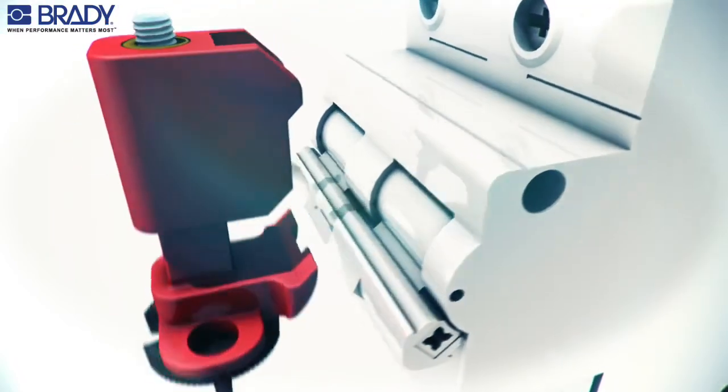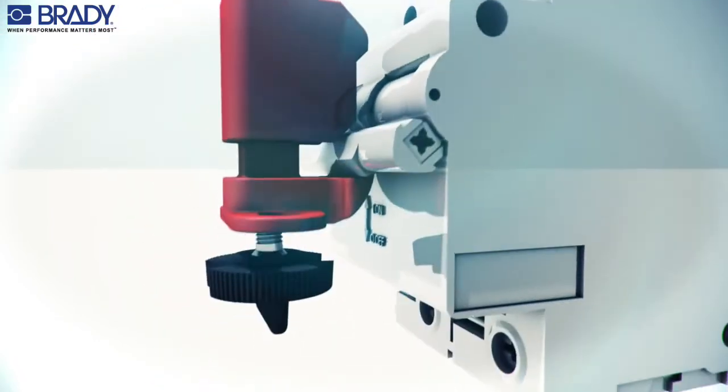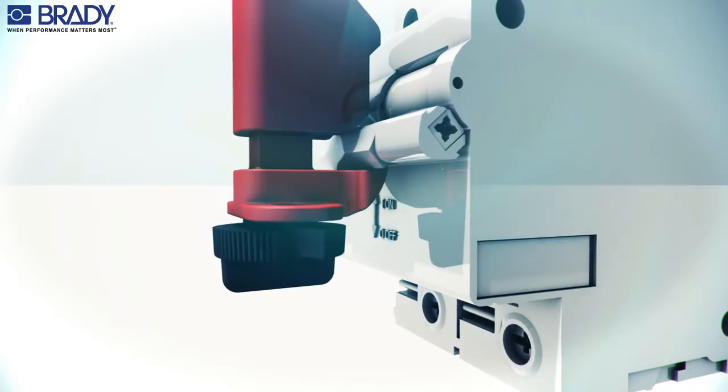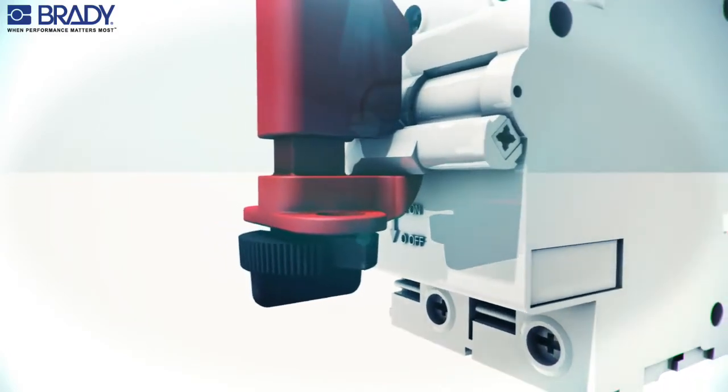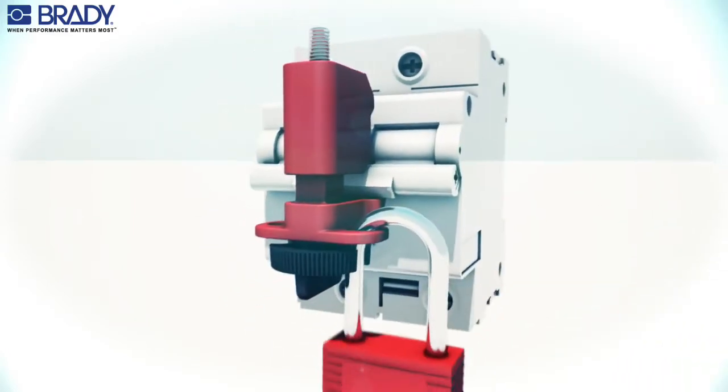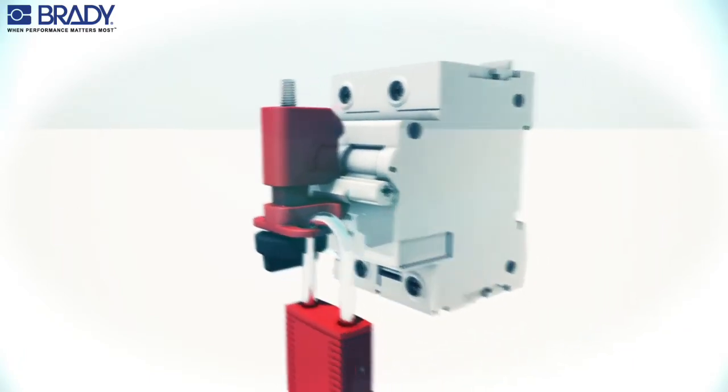For the tie bar method, place the circuit breaker in the off position. Put the metal clip under the tie bar and between the poles. Rotate the thumb wheel clockwise to secure the lockout device to the circuit breaker. Insert the padlock through the hole to secure the device in the lock position.